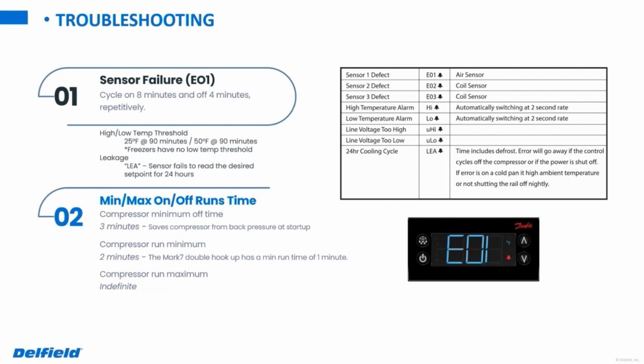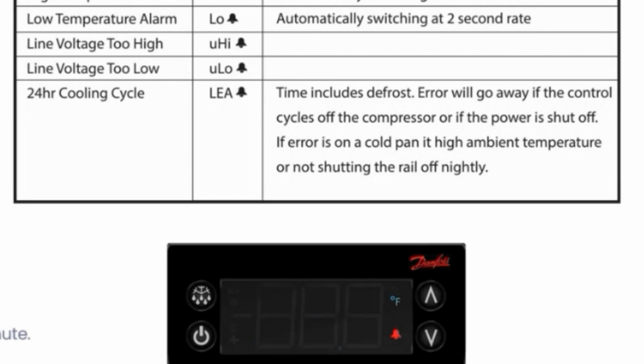And then you'll see the different high and low voltage alarms on there as well, as we talked about a few minutes back. And then LEA is something that we get quite a few questions about, kind of the function of that on the display. Basically, LEA means that the unit is at a call for cooling for 24 hours, but it hasn't satisfied the thermostat. So normally if we have LEA showing on the display and you're giving me a call and telling me, hey, I've got this LEA on the display, what does it mean, what should I do? The first thing I'm probably going to have you do, and we'll talk about this in a little bit too, is a real-time probe reading.